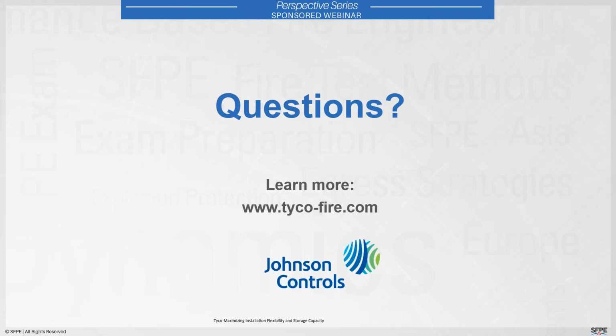The next question we have here is, what is the maximum storage or ceiling height ESFR sprinklers are currently listed or approved for? Should I back up and repeat my presentation? No. Yep. So ESFR sprinklers, within NFPA, if you go to NFPA 13, the highest ceiling height that ESFR sprinklers are approved for is 45 feet.